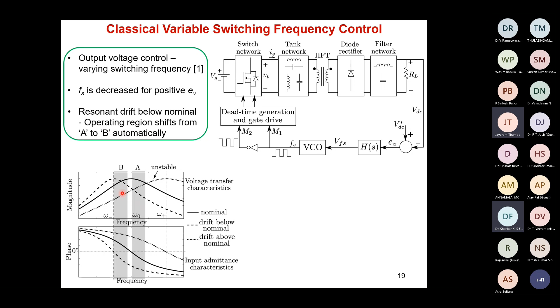Now, what we analyzed for this variable frequency control is that automatic regulation of the voltage is possible as long as we are in the negative slope region of this characteristic. Because what the controller does - if it sees the error is positive, it will decrease Fs. That phenomenon will regulate as long as you are either in region A or region B. So if your characteristic shifts from the bold line to drift below nominal, the operating region will shift from A to B and you will continue to regulate, no issues.